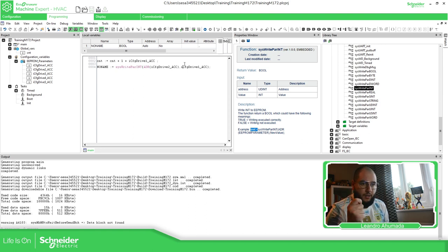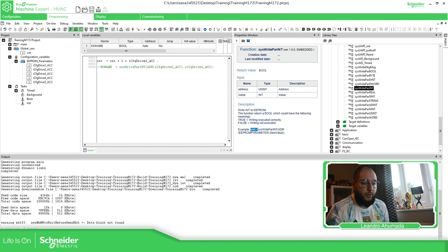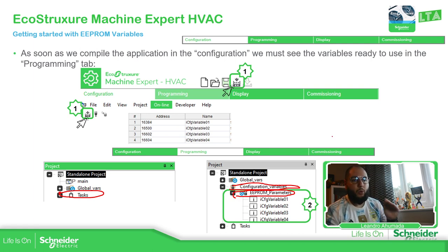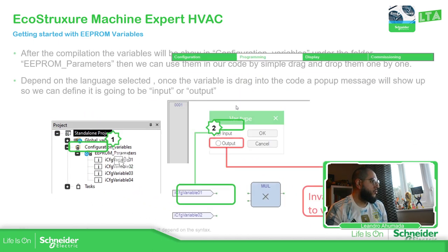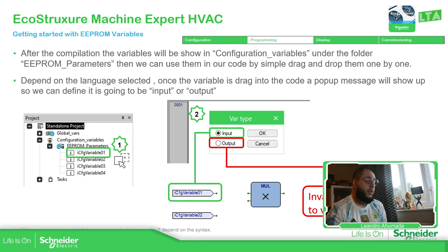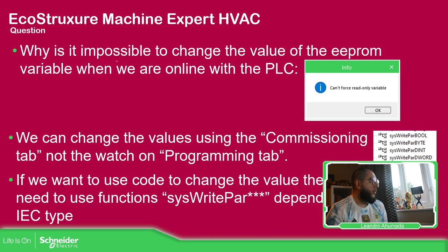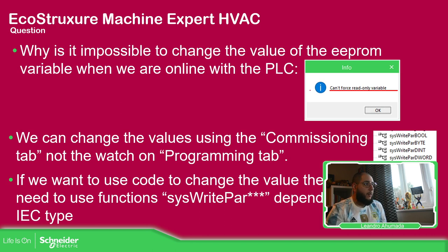This is the complete approach. The key point is that you cannot modify EEPROM values directly via code. The same drag-and-drop approach applies for variables in your code. If you try to write directly and go online with the controller, you'll get the 'Invalid Access' message. However, you can change the value using the Commissioning tab, or via code using the sysWritePar functions.